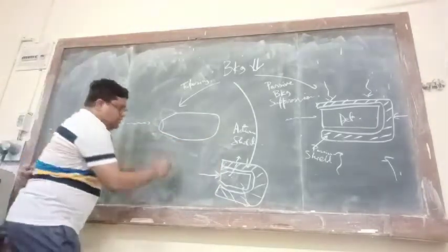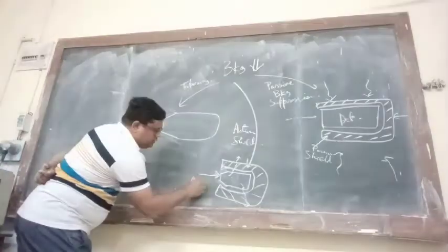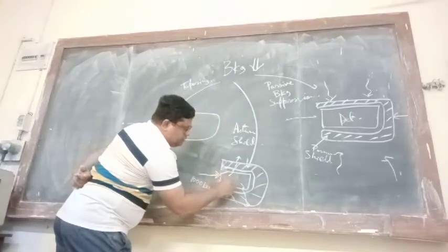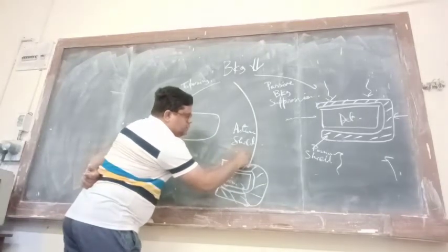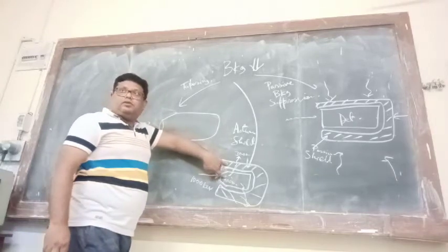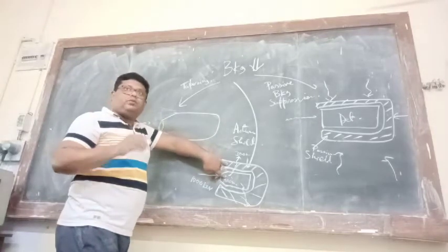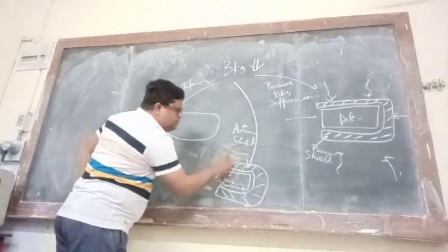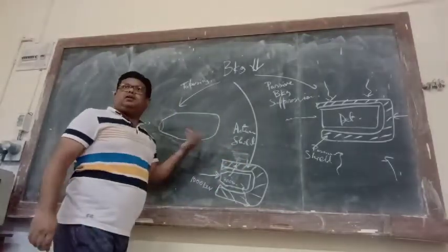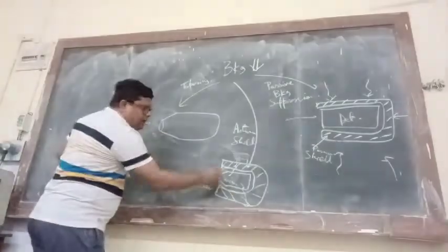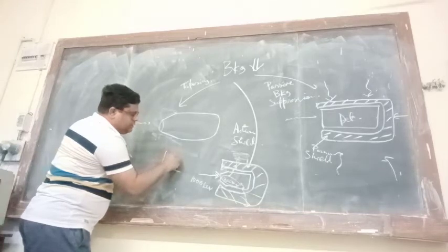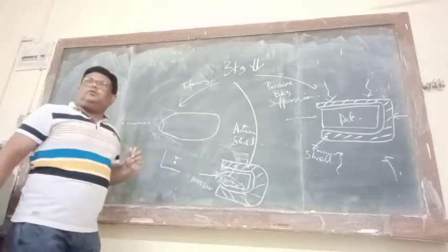Example. Suppose 1000 keV, again the classic example. Now 700 is absorbed and 300 escapes. If I don't use the anti-Compton condition, this 300 will get absorbed over here. In the spectrum, I will just see a count at 700 keV, but this will correspond to background.